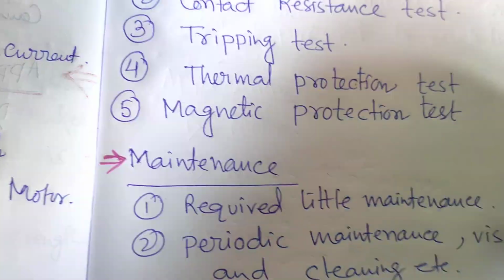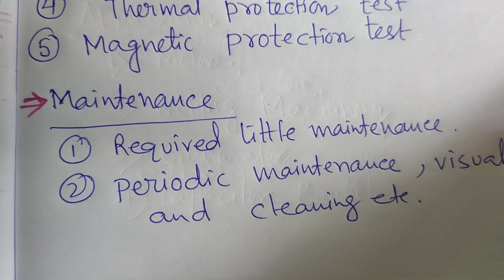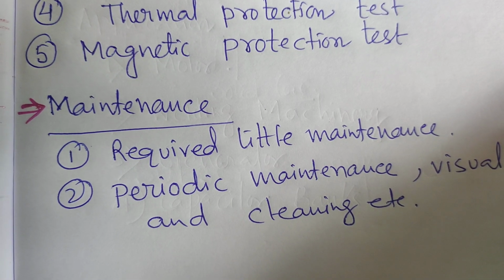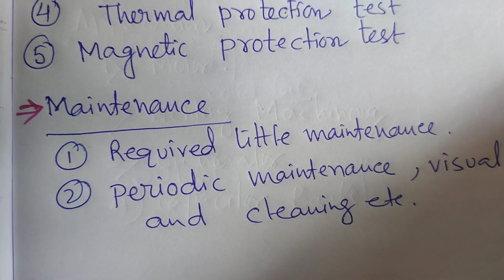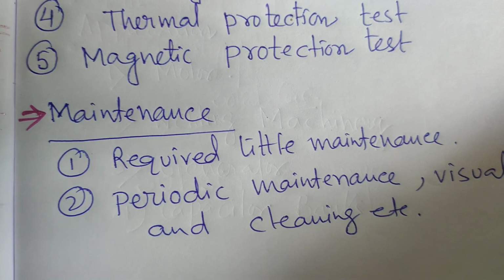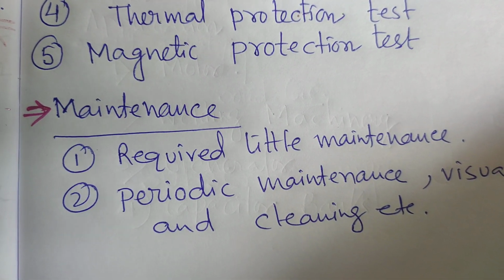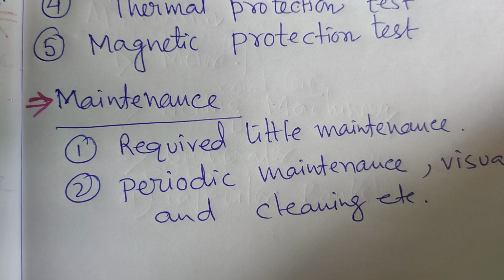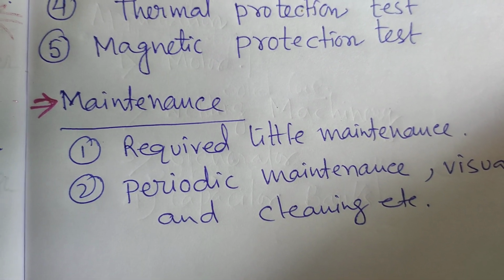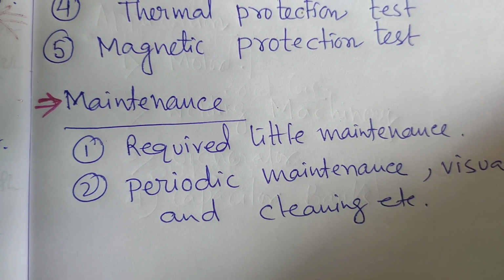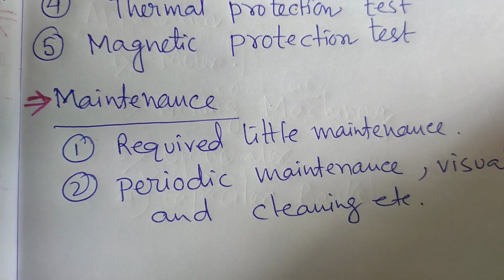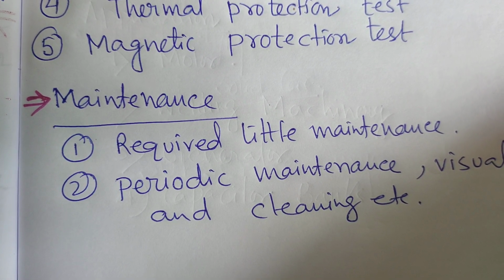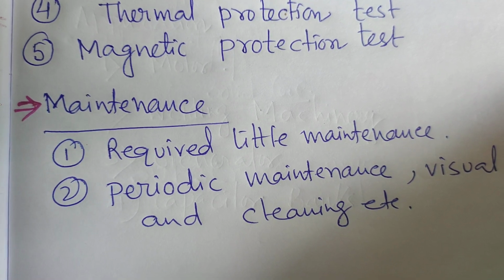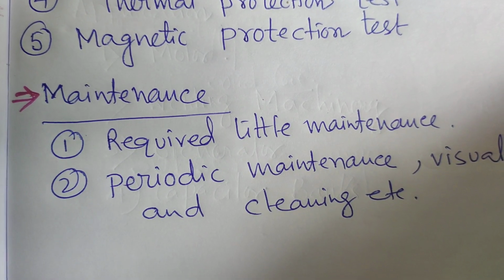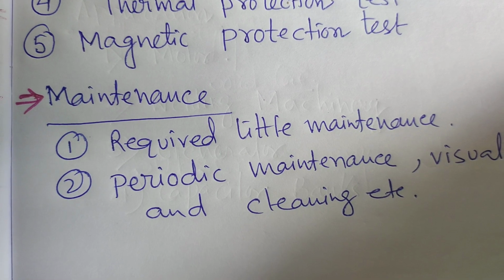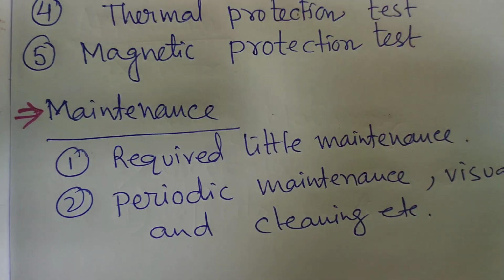As for maintenance, the MCCB requires only little maintenance because it is almost maintenance free. It is inside the molded case, and arc extinguishers are also there. If you open the upper molded case and clean inside the carbon deposits and different types of hydrocarbons, the MCCB life will be enhanced. So periodical maintenance, visual checking and cleaning are of great importance.